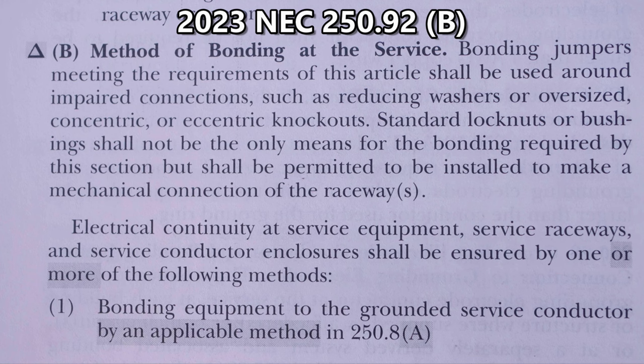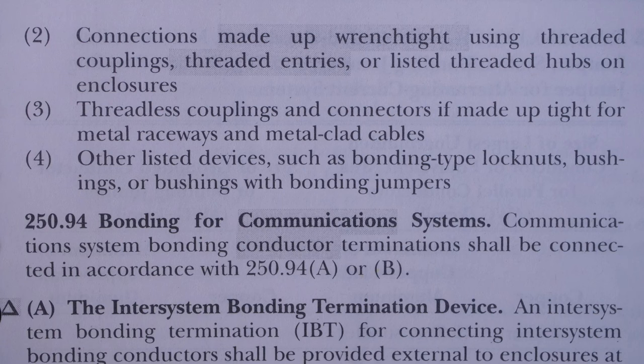Electrical continuity at service equipment, service raceways, and service conductor enclosures shall be ensured by one or more of the following methods. 1. Bonding equipment to the grounded service conductor by an applicable method in 250.8A. 2. Connections made up wrench tight using threaded couplings, threaded entries, or listed threaded hubs on enclosures. 3. Threadless couplings and connectors if made up tight for the metal raceways and metal clad cables. 4. Other listed devices such as bonding type lock nuts, bushings, or bushings with bonding jumpers.